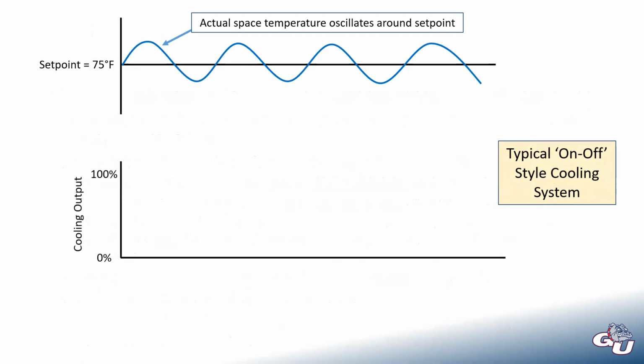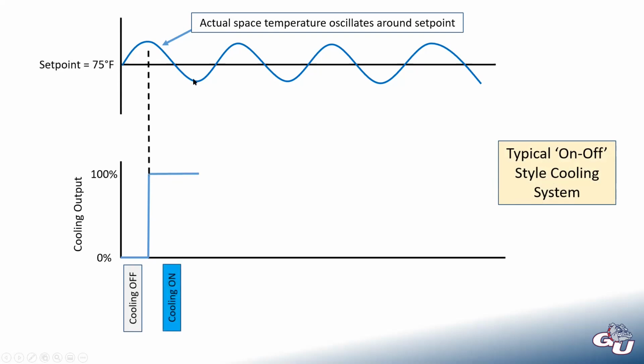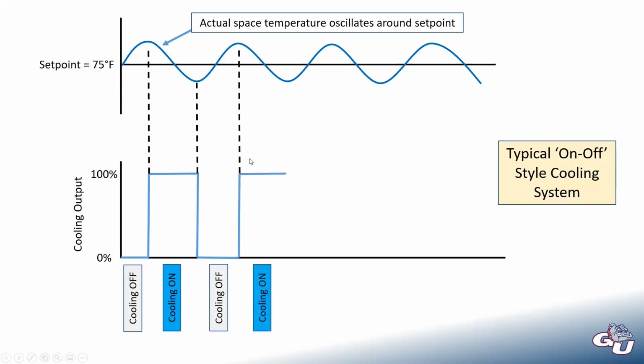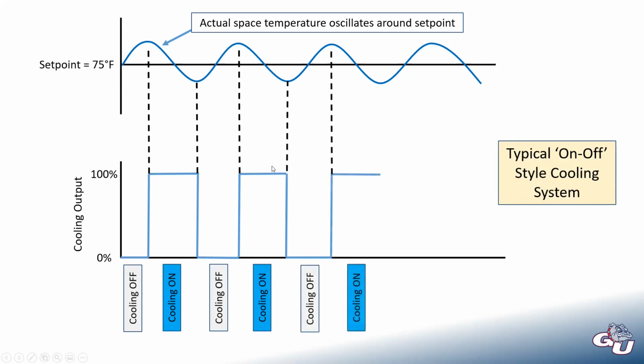And the cooling system, if we're looking at the cooling output, well, let's say our cooling system is off, and then as our temperature rises, that sends a signal to say, hey, turn our cooling on. And now we get 100% output. It maintains that 100% output for a while. And since our air conditioner is running, our temperature starts to drop. And eventually it will cross whatever temperature we're trying to maintain. And it will undershoot it a bit until it gets to the point where we say, okay, that's enough, turn it off. So the cooling system goes completely off, temperature starts to rise again, cooling system turns on, and it just keeps doing this all day long.